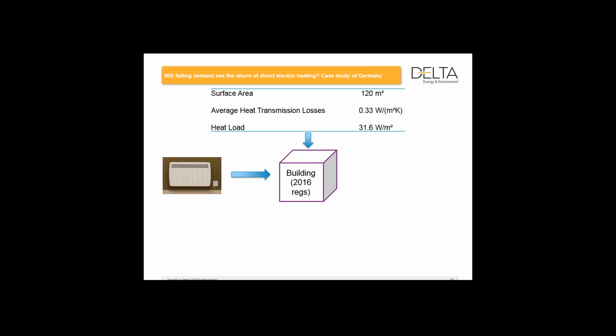Minimum insulation, no heat recovery, no solar thermal hot water production. A direct electric system in such a building, even with the new primary energy factor, would definitely not meet the requirements — it would exceed the reference building's demand by more than 40 kilowatt hours per square meter per year, and also fail the renewable energy criteria.